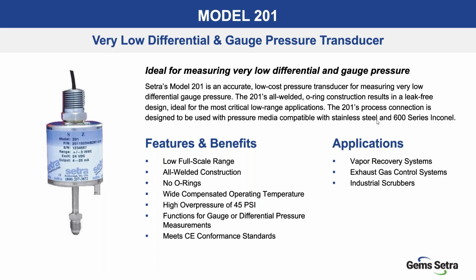The features and benefits here are around low full-scale range, all welded construction, and, as I said, no internal O-rings. Available to operate over a wide temperature range, yet able to handle a high overpressure for a very low pressure operation. That ensures that if the customer were to inadvertently apply an overpressure of 40 to 45 PSI, the unit would come back to its original state and not drift. Common applications served include vapor recovery systems, exhaust gas control systems, and industrial scrubbers.